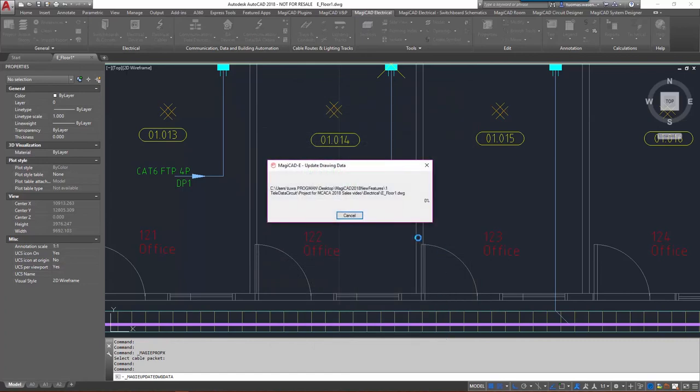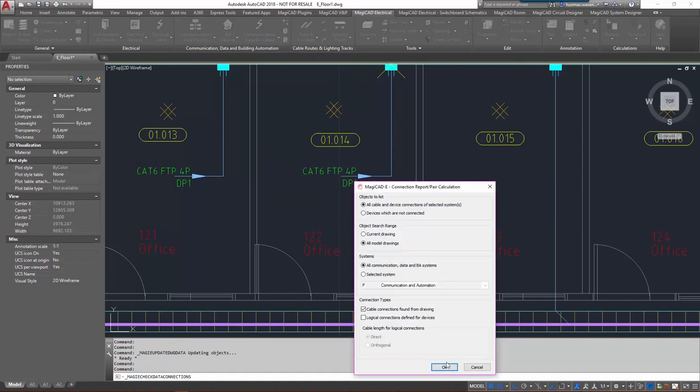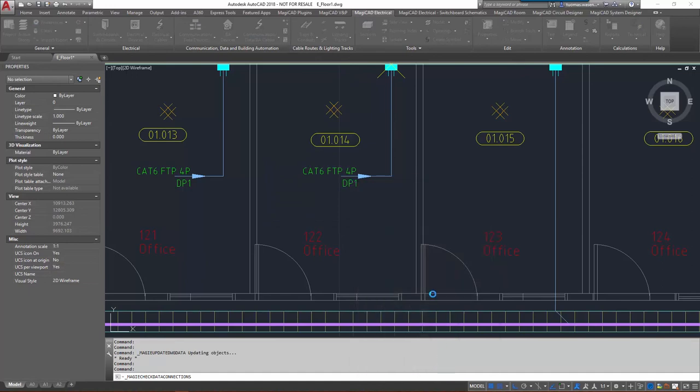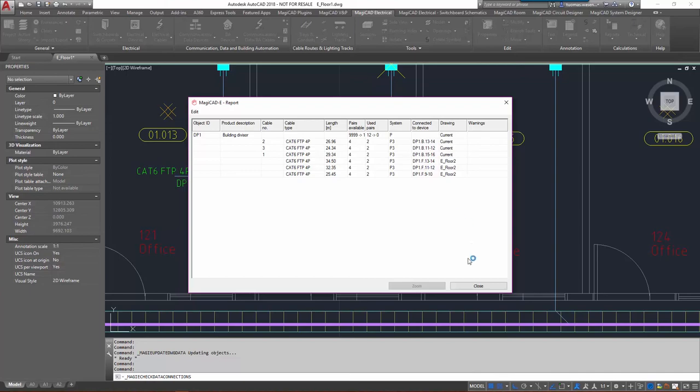Okay, we'll just again update the same data from the drawing and also let's run the connection report once more. Now we can see that the cable numbers have been updated, all the devices have the ID here, and I'm pretty happy with that one.